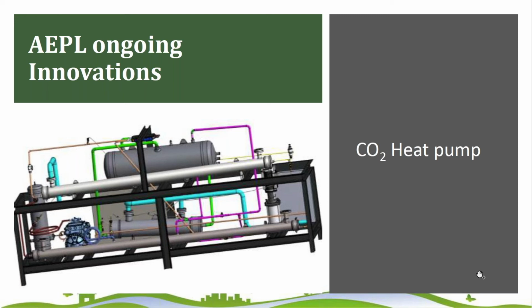We are building this one for a kitchen application, and the beauty of this product is that in a single pass we can heat from 24 degrees Celsius to 90 degrees Celsius. On the hot side the heating capacity is 141 kilowatt, and in parallel on the cold side, from 12 degrees Celsius to 5 degrees Celsius, the cooling capacity is 102 kilowatt. We are doing this in collaboration with NTNU Norway and SINTEF Norway. This is the best eco-friendly refrigerant with a high COP that is possible, and this will be the first CO2 implementation in India. So next slide.